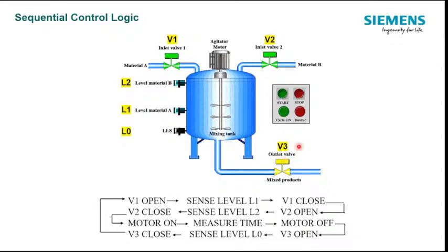Once V3, my drain valve, has been opened, the mixed product will start flowing and getting drained. Once it reaches the lowest level L0, there the limit switch is there whose NO/NC contact again I will take as an input to my PLC to close V3 and open V1.